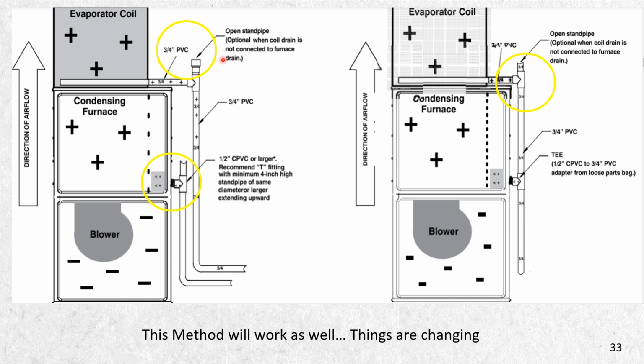Here's the other way. This is a standpipe without an end cap, and we'll show you the difference why that is. But you see, it's positive here and positive coming down here, so you have to have an open standpipe here, and here you can do it two different ways. One is a 1/2 inch or larger recommended T-fitting with a minimum 4-inch height standpipe. So if you do a T, they really want you to come up 4 inches off of that and leave it as a standpipe as well.